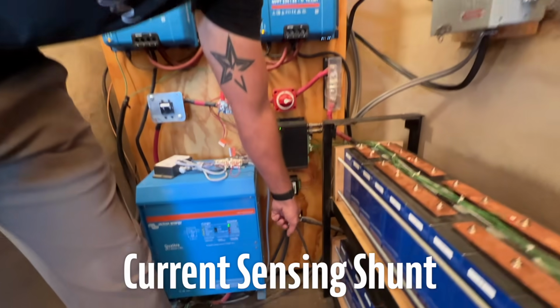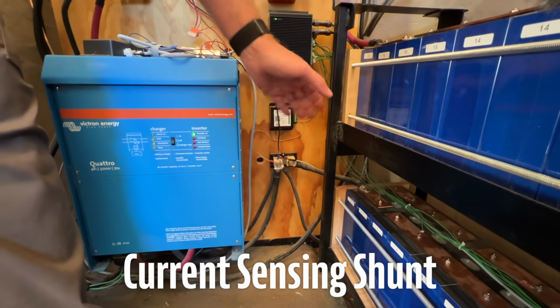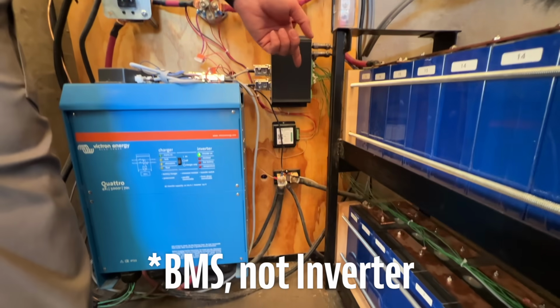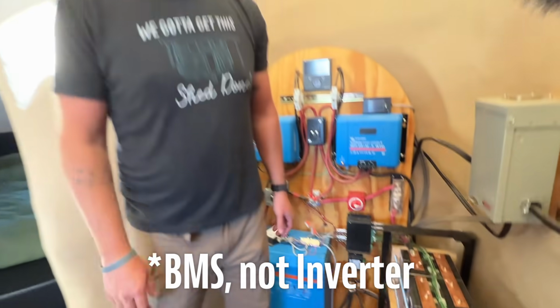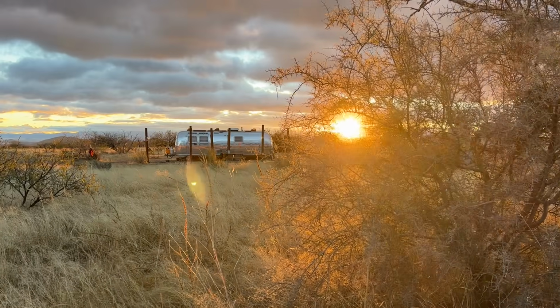And then finally, from the negative post on the battery, you're going to run through your current sensing shunt, which is also connected to the inverter, and it looks for state of charge. One important note: when you're installing any of these circuit breakers or switches or fuses, they should all either be removed or turned off while you're installing until you're ready to boot the system.